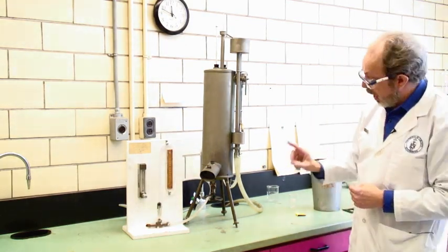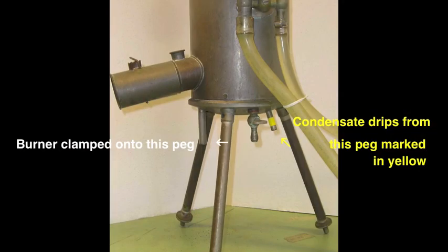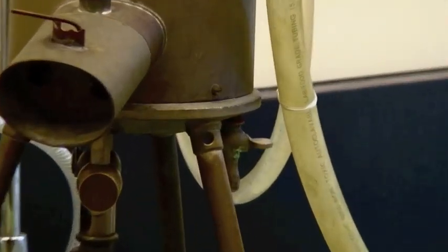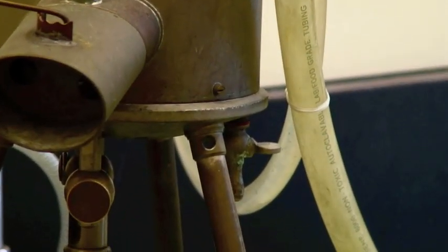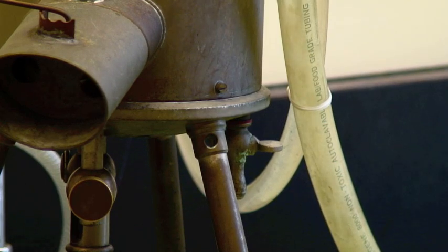It takes a while for this to happen but this nozzle here, not the one with a tap on it, but the open nozzle here is where the condensate will start to drip out. Until you have dripping from this nozzle there's no point in taking any readings. It takes about 10 minutes.